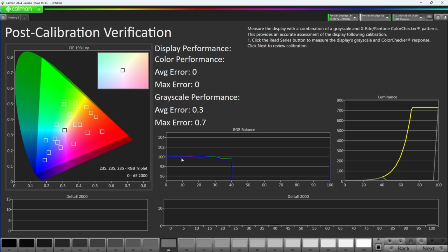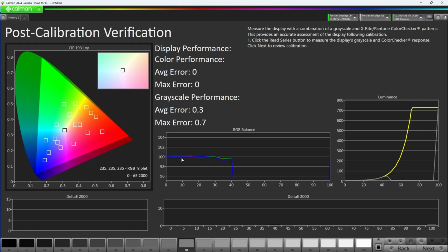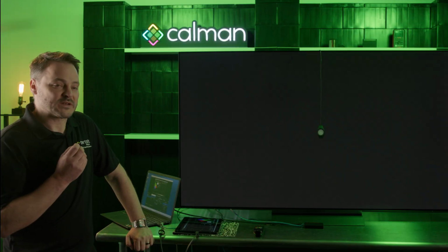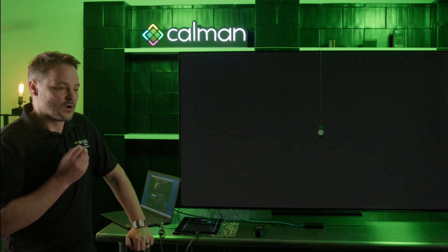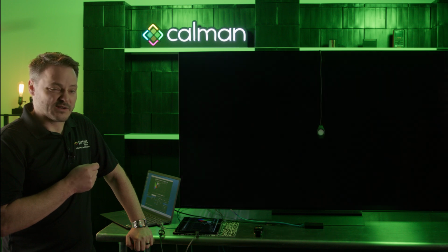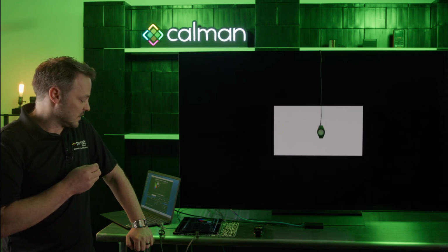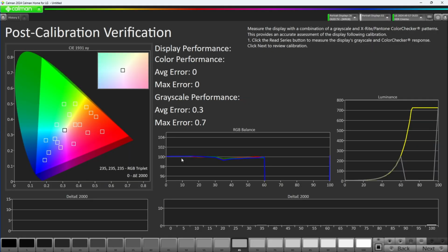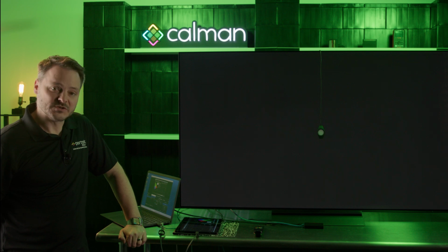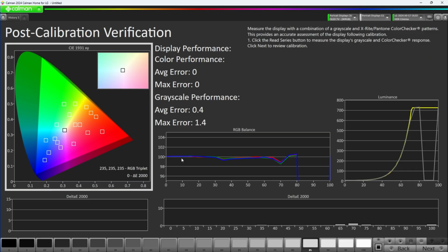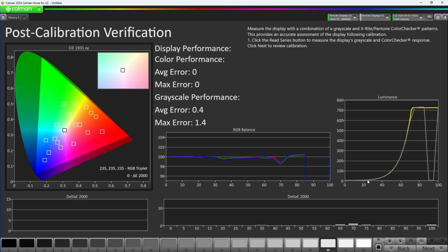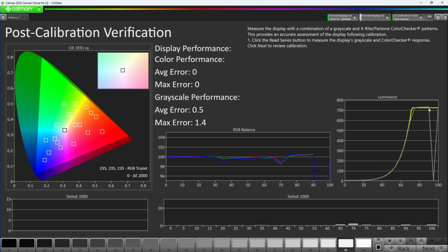For our color checker, do note that we probably will see a little bit higher errors in our HDR color checker than we would on SDR, for example. But what we'll expect to see is that all of the measured values are going to come very close to the target squares, and that we should have DEs close to or under 1 in almost all those values. All right, so those grayscale measurements are completing, and you'll notice that the tracking along our luminance targets here is very, very good, and that our red, green, and blue balance are all balanced right along that 100 line.